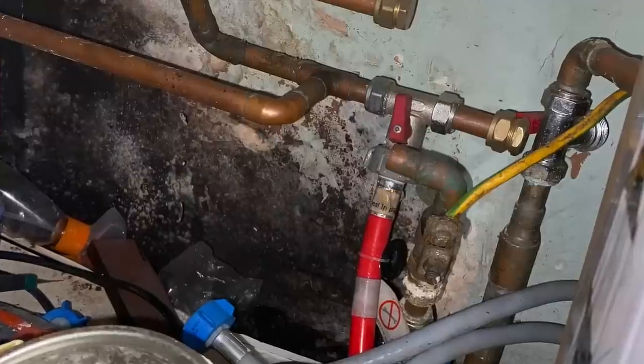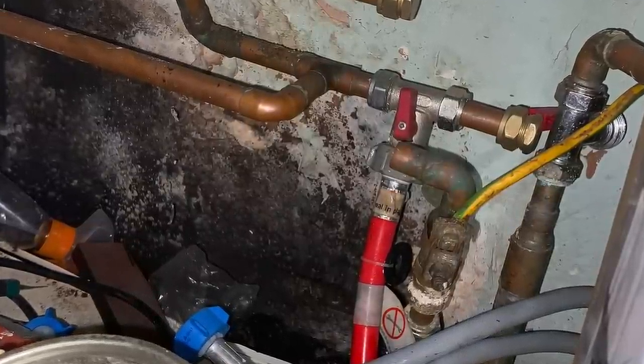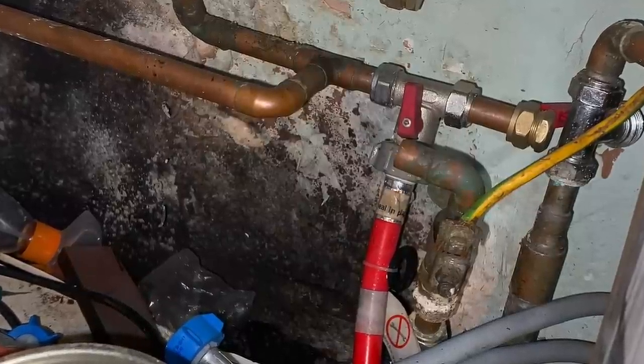We were at the bonding stage. You measured the protective bonding conductor and got a super high reading. Basically I had a bonding conductor inside the consumer unit coming into the earth bar. I disconnected it, tested it to the local pipework under the sink — I could see the bonding connection — and it was like 20-odd ohms. That's a bit high. We were expecting something 0.05 ohms or below.